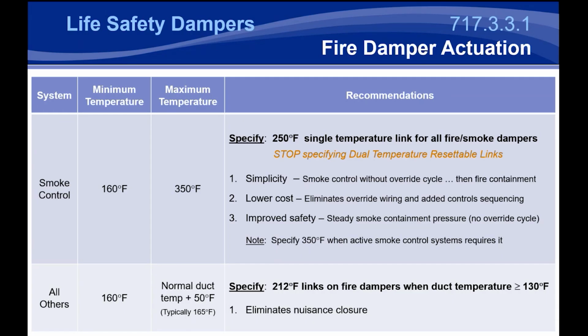So that's something I recommend engineers link to the rating of the smoke control damper. Now, of course, if your smoke control system is rated to 350, you've got fans that'll work up to 350 continuously, everything's set up for that, then by all means certify the damper at 350. There are options available for that, but there is an added cost risk when you're dealing with that. I also recommend engineers not specify a damper rating at 350 if it's not used in a smoke control system. It's going to close at 160 or 212 typically, well below 250. So there's really no added benefit to having a damper rated for 350 as it will never operate at those elevated temperatures.